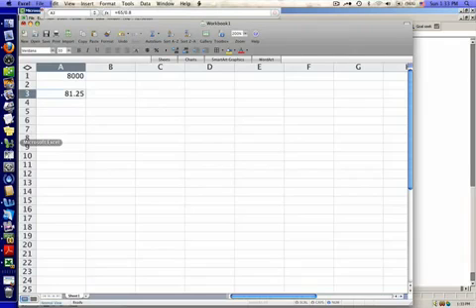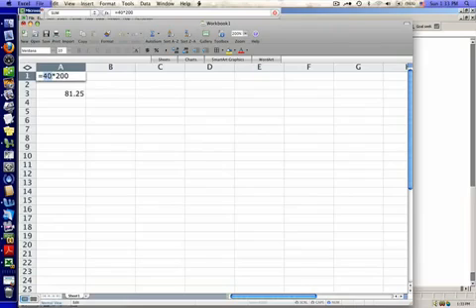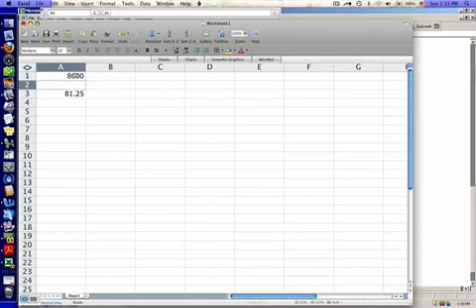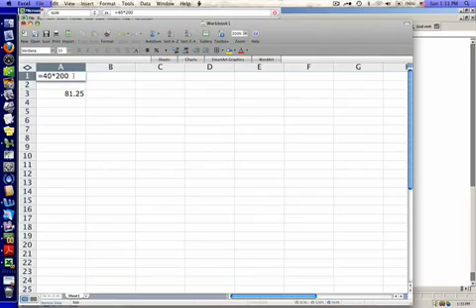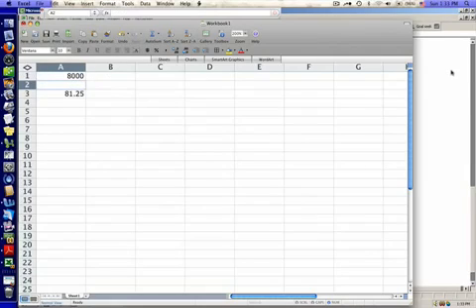First, it wants to know how much the system is going to cost. We know we want a system for about 40 gallons of hot water per day, so that's going to be our solar storage capacity and our collector area. Using Excel as a calculator, we get 40 square feet multiplied by our current cost factor. For a small 40 square foot system, that's about $200 per square foot, giving us $8,000 total.